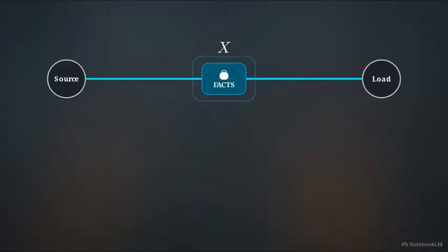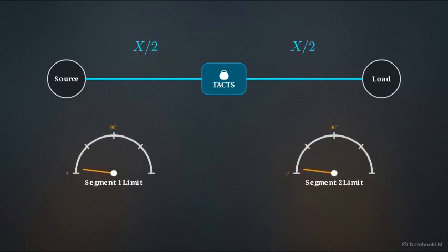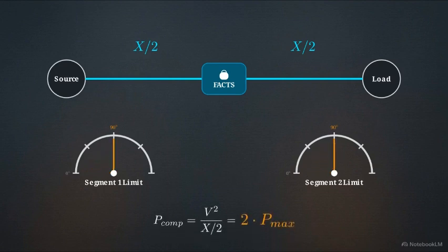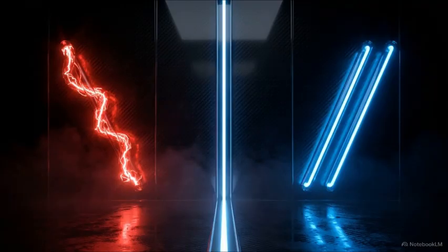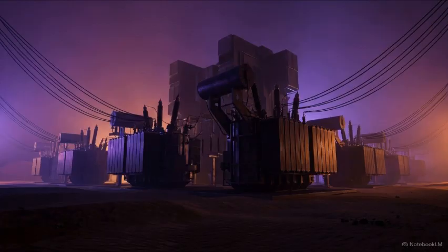By anchoring voltage exactly in the center, the FACTS device splits the transmission line mathematically into two separate lines, each with half the original reactance. Allowing each isolated half to hit its margin independently elegantly doubles the entire system's maximum power transfer limit. Injecting high-speed electronics at the literal halfway point turns one highly unstable boundary into two perfectly stable grids. And it achieves this without laying a single new wire.